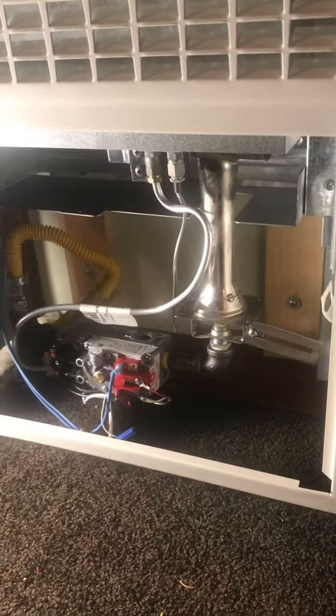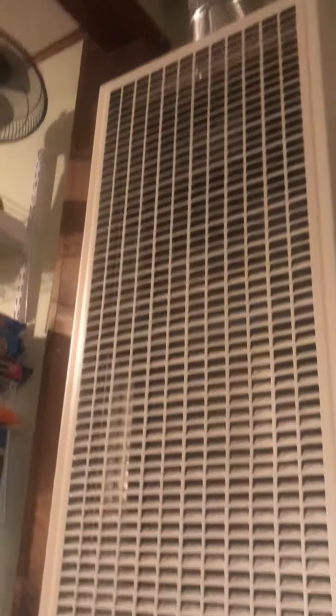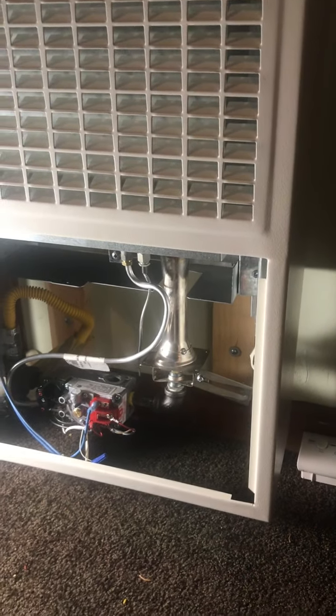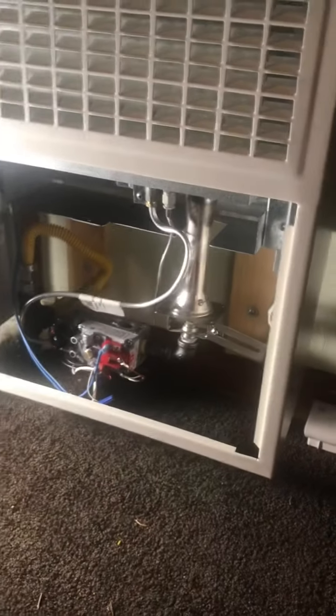The point of all this is Steve today said to look at your wire nut that has the white cable from the thermostat going into — or intertwined with — a safety cable, the blue cable here, going up the furnace to where the safety switch is right about there. That safety switch basically shuts the furnace down if the flue gets blocked, preventing hazardous toxic fumes from coming into the house. Here's what he suggested: renew all connections. I took that wire nut off, cut the old part of the blue wire and the old part of the white wire that were once intertwined, and made a new connection.